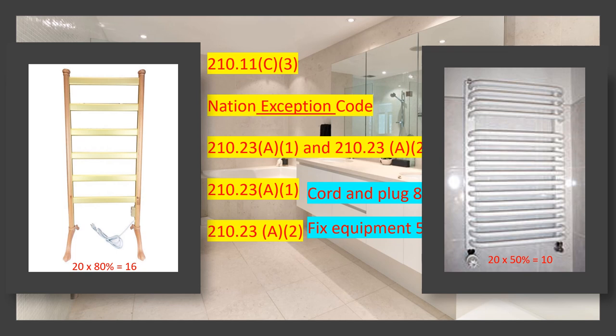Now let's talk about a different scenario: am I allowed to run the bathroom lights off of another circuit, like the hallway circuit? The answer is yes — you are allowed to tap lighting from anywhere. You may have to do this if you meet the 50% or 80% rule. For example, if you had a fixed towel bar that was 11 amps, you could not run lighting off that bathroom branch circuit. In that case, you could pull lighting from the hallway, but you couldn't run receptacles or anything else off that other circuit.